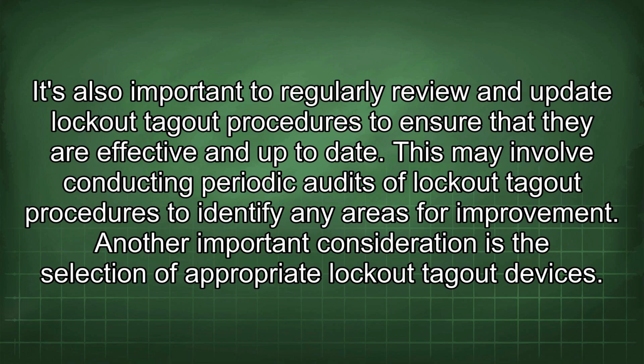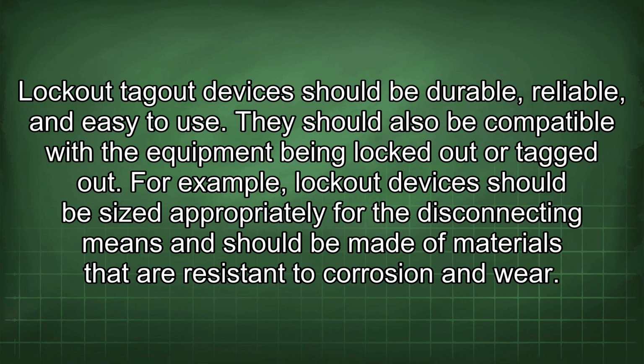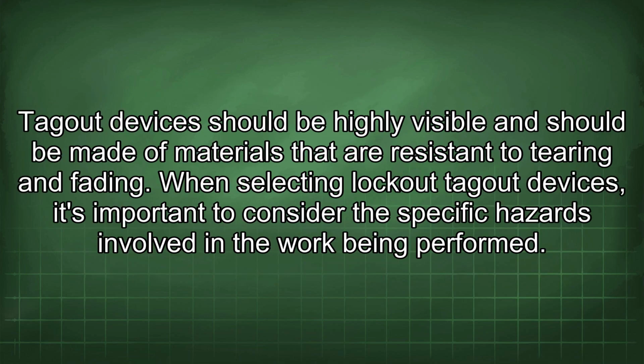Another important consideration is the selection of appropriate lockout tagout devices. Lockout tagout devices should be durable, reliable, and easy to use. They should also be compatible with the equipment being locked out or tagged out. For example, lockout devices should be sized appropriately for the disconnecting means and should be made of materials that are resistant to corrosion and wear. Tagout devices should be highly visible and should be made of materials that are resistant to tearing and fading.